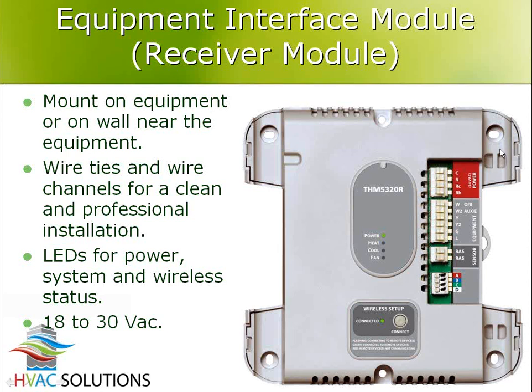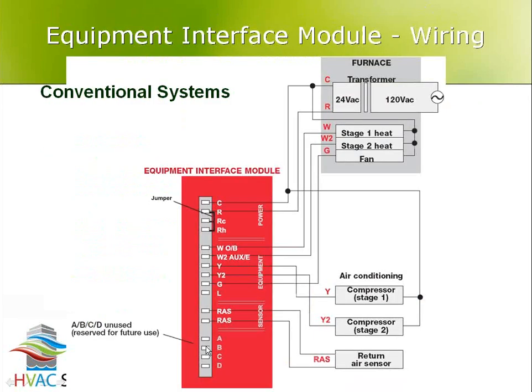It uses 24-volt AC power just like normal zoning panels use, and this guy will physically wire over to the equipment. So this here just shows you an example of it here. And you guys know how normal wiring goes. So heat 1 is W, heat 2 is W2, fan is G, cooling is Y, and if you have second stage cooling, it's Y2. Return air temperature sensor is 2 wires.